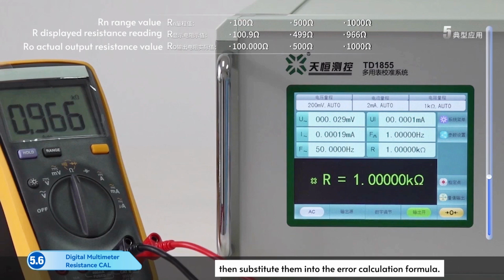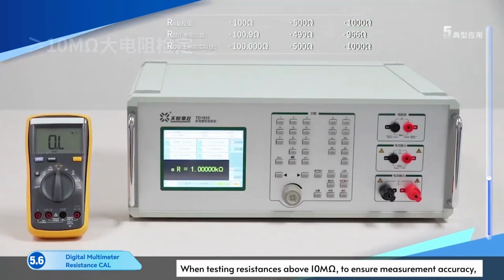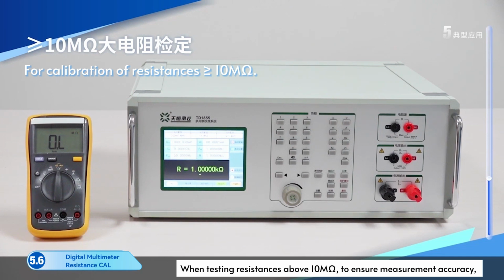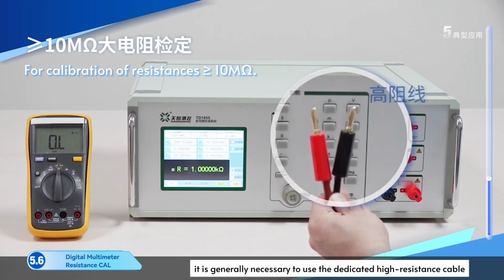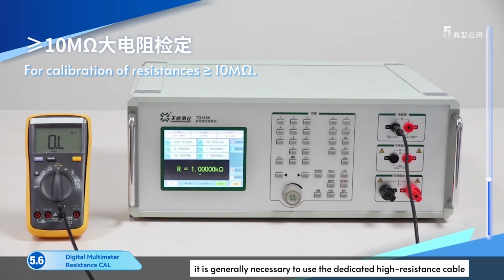Then substitute them into the error calculation formula. Calculate the errors for each calibration point and record them. When testing resistances above 10 megohm, to ensure measurement accuracy, it is generally necessary to use the dedicated high-resistance cable.